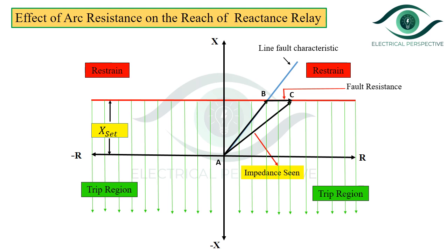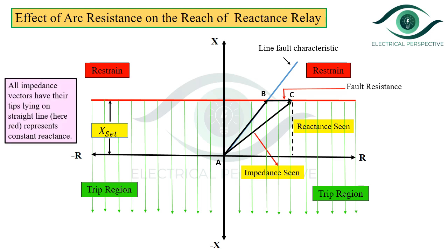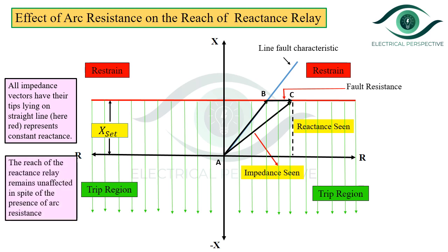Thus the reach of the reactance relay remains unaffected in spite of the presence of arc resistance. This is expected because the relay responds only to the reactive part of the impedance seen and trips only if that reactive part is less than the preset value X_s. All impedance vectors have their tips lying on the straight line representing constant reactance, confirming that the reach of the reactance relay is unaffected by arc resistance.